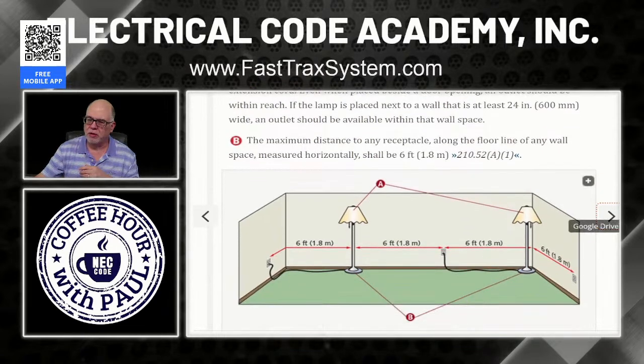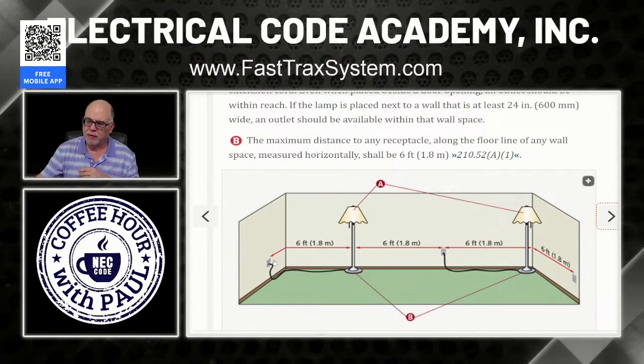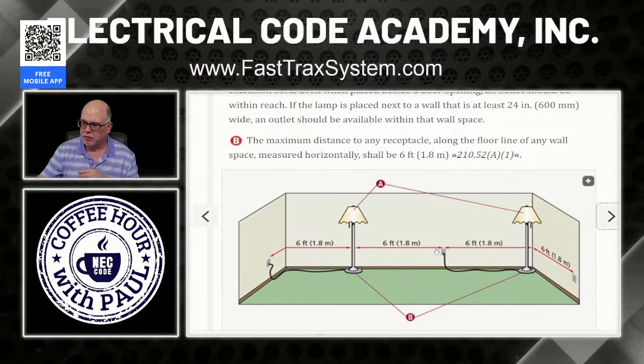So here's your typical layout in your room. Say it's a doorway over here, and you've got your receptacle within 6 feet of the doorway. And then it goes from here to here. That is 12 feet between these two. If I put a lamp right in the middle, that 6 foot cord would reach this receptacle, or this receptacle. Same as over here. So that's all we're saying.